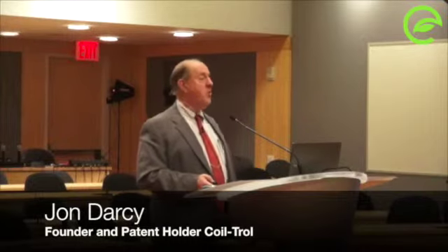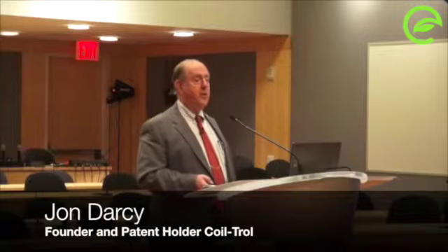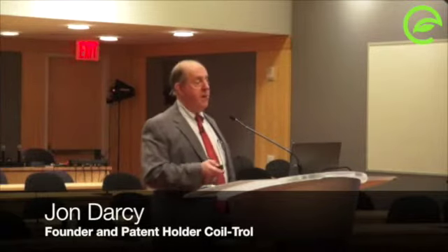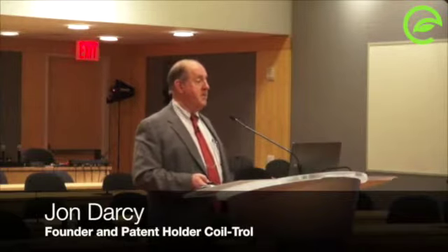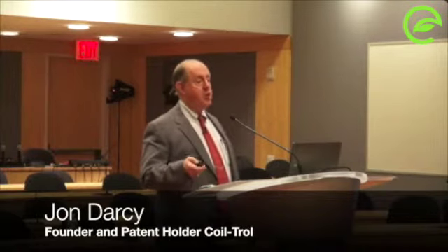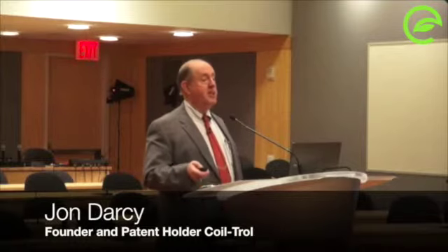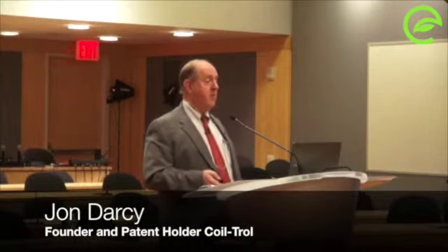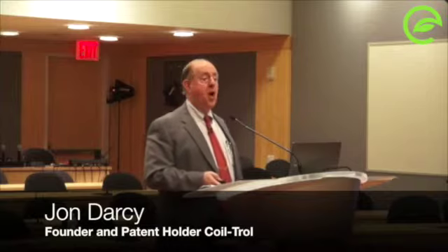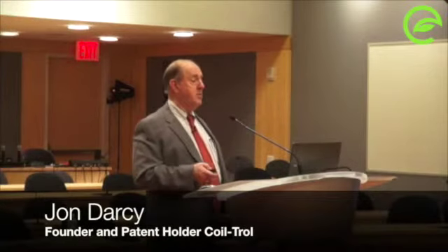We found out that I could increase the delta T across the chill water system to 20 or 25 degrees. Now I can't do that with the chillers, so now my limit is no longer controlling the coil on the air handling unit. My limit now becomes what is my chill water plant capable of doing from a delta T standpoint, okay? And by the way, if you slow the flow down through a chiller, you can easily get 17 degrees from it, okay, without going outside the design operating parameters for a chiller.